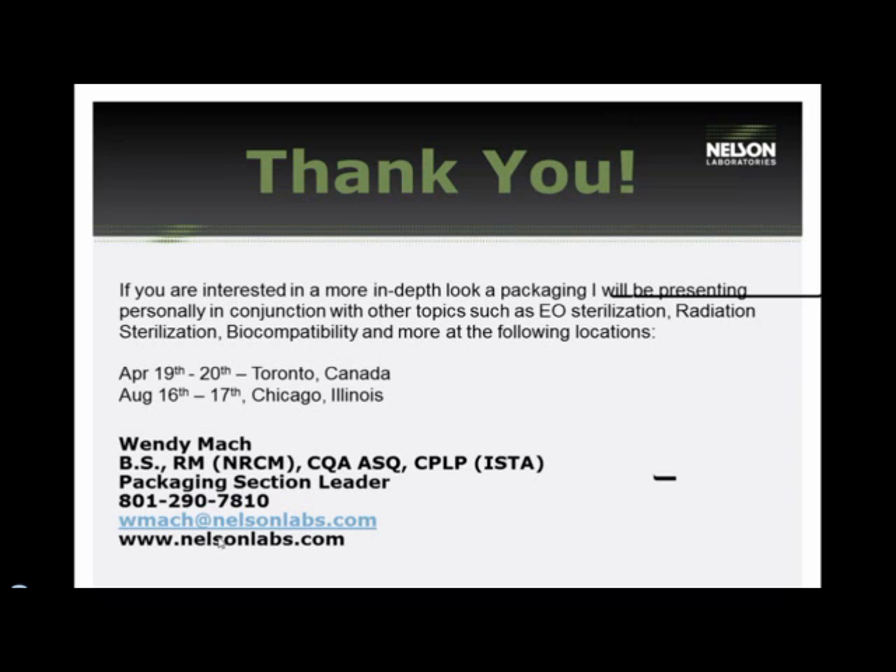How is the FDA feeling about using medical grade paper instead of Tyvek for medical device packaging intended for EO sterilization? It depends on how the validation is driven. You can use paper for sterilization — the validation for the packaging is exactly the same. It just follows through demonstrating integrity, microbial barrier, etc. As long as the EO and the paper are compatible, you should be fine.